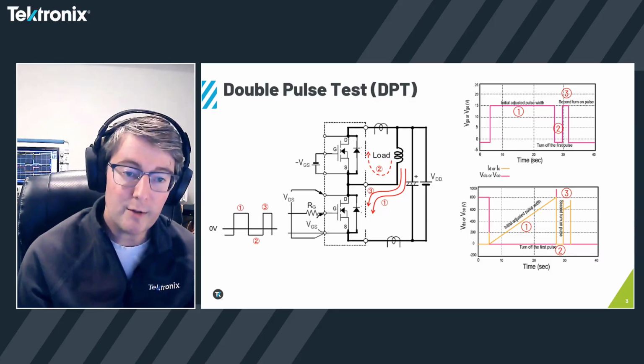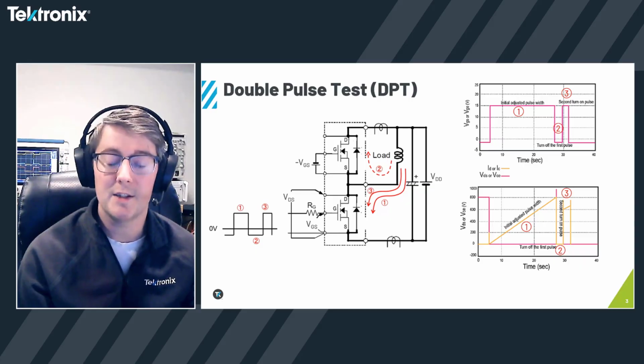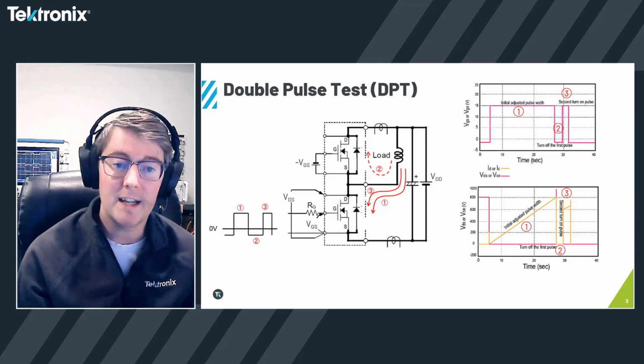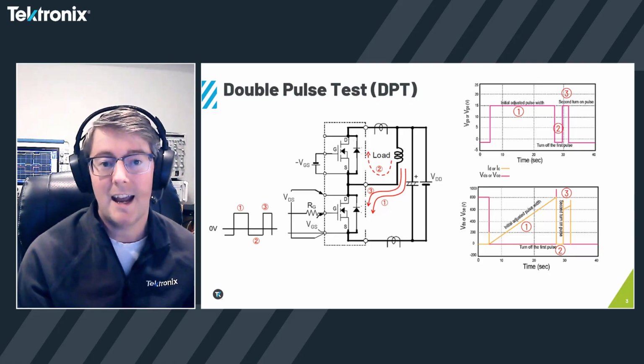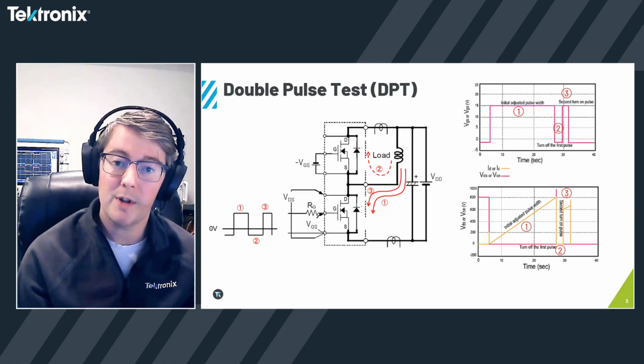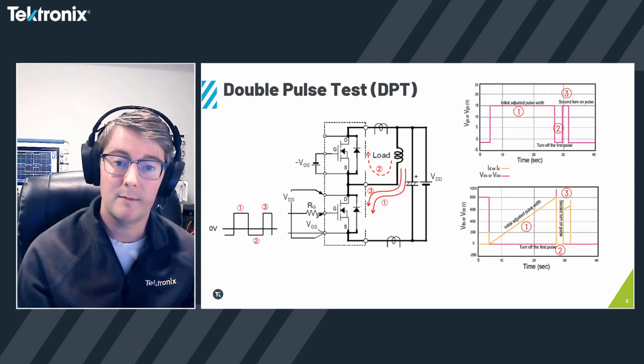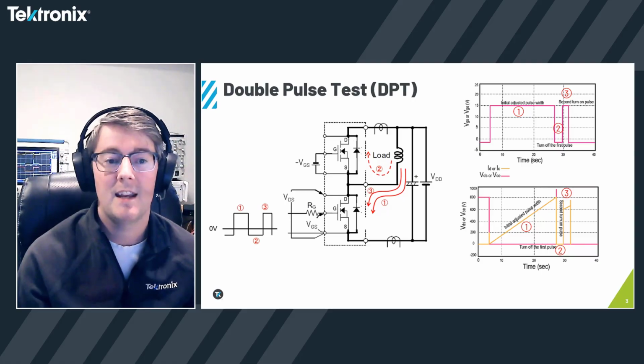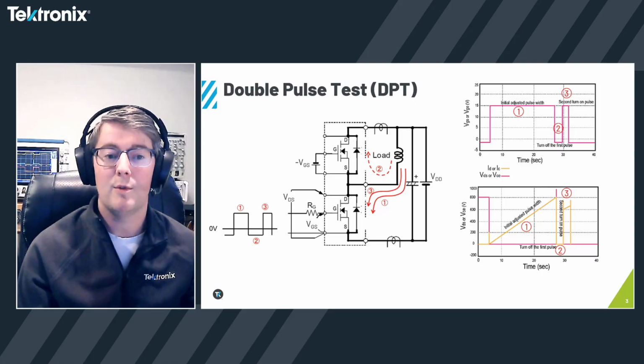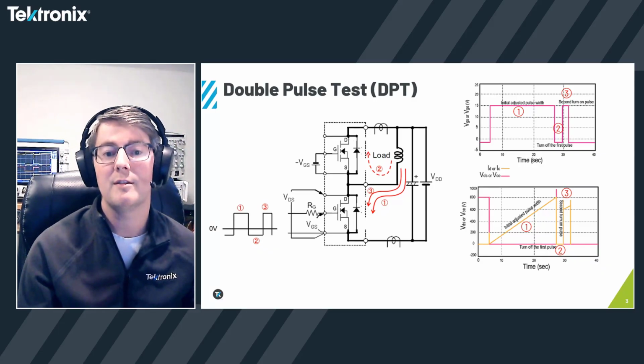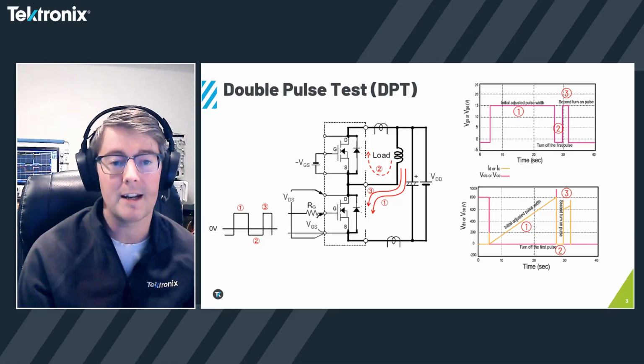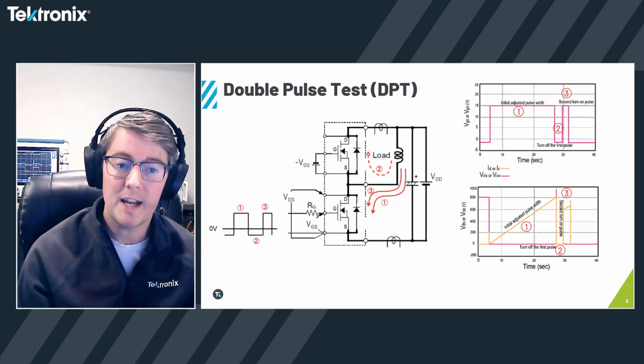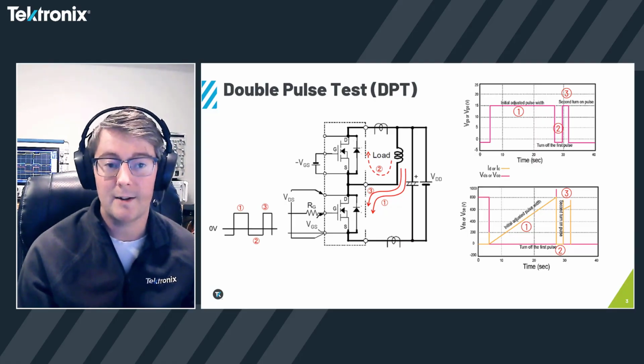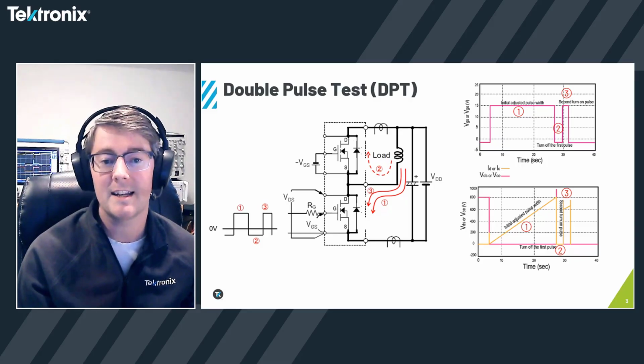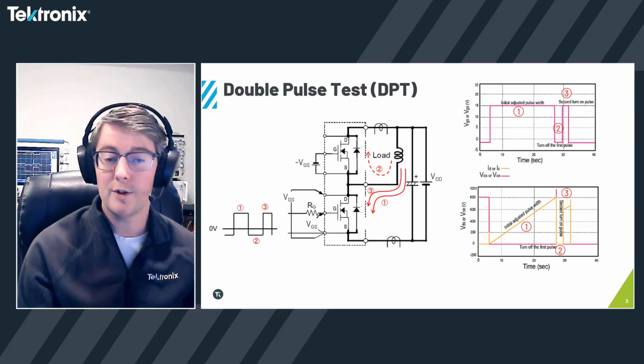The general sense of double pulse testing is two different pulses injected into the low side FET's gate. The intention is to use the first pulse to charge up the load inductor to its desired state. There's a brief period of dead time where the low side FET is turned off and the high side FET goes into a freewheeling operation mode with its body diode included. Then the third step is when the pulse turns back on, or the second pulse is injected into the low side gate, at which point the FET turns back on.